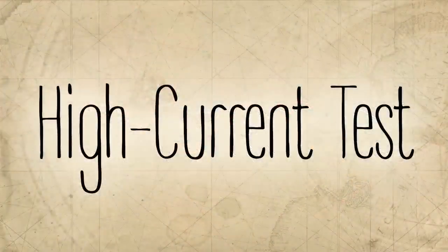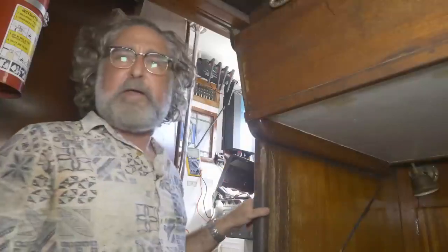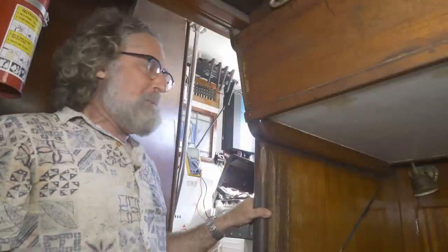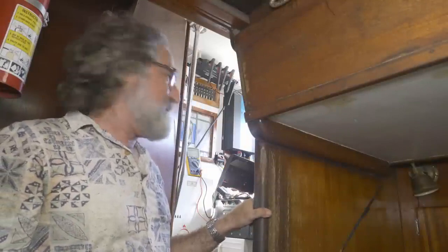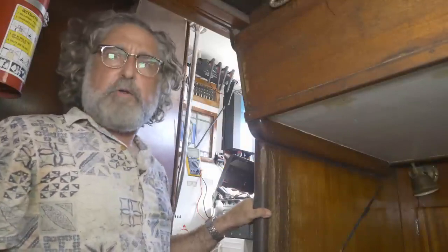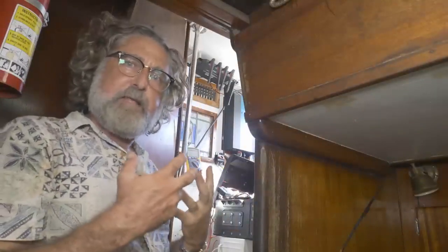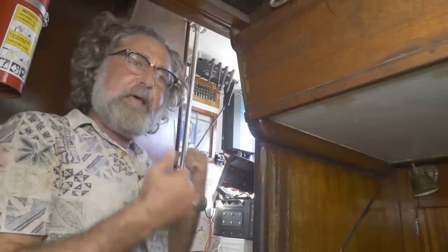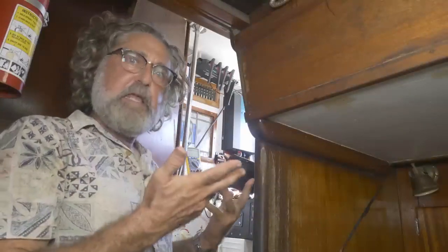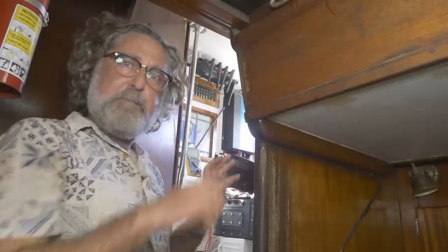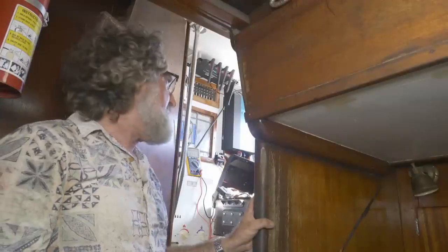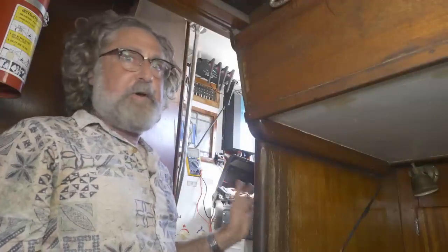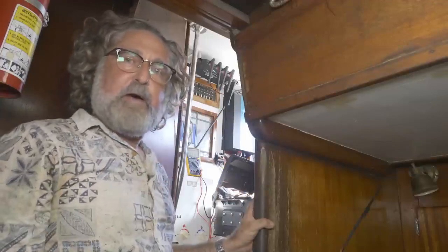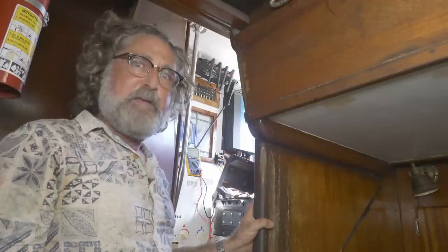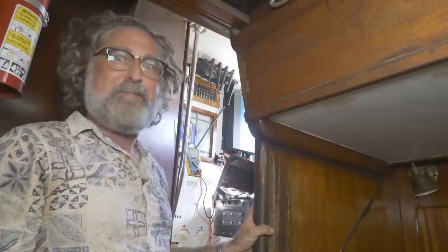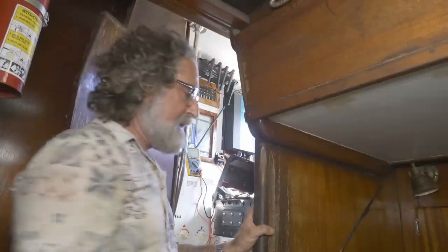All right, we're back here in the aft cabin now. I've got this massive battery hooked up to my inverter. My inverter's only a 3,000 watt inverter. And I was wrong earlier when I said this battery is only set up with a BMS that can put out 200 amps. They actually rated it 250, and we found from the BMS itself a sticker that says 300. This inverter, I can only put a little over 200 amps out of it through the inverter. So, well, that's a lot of power. So we're going to do the test at that level.